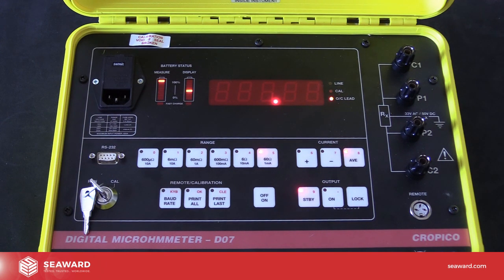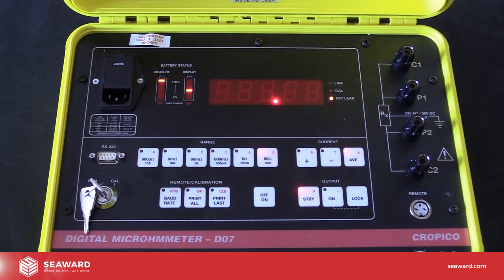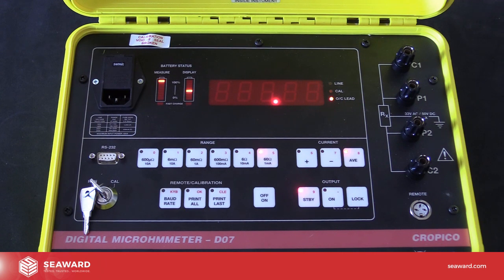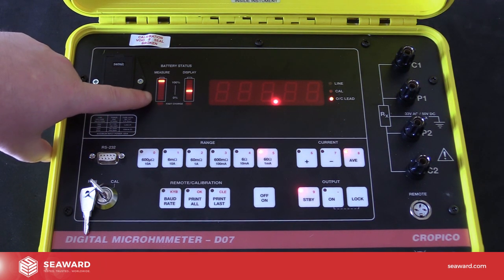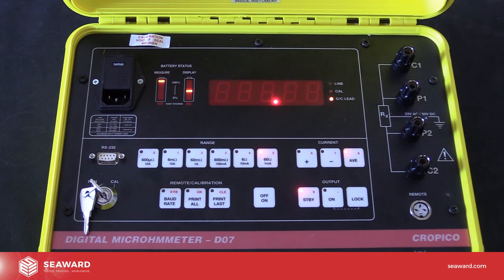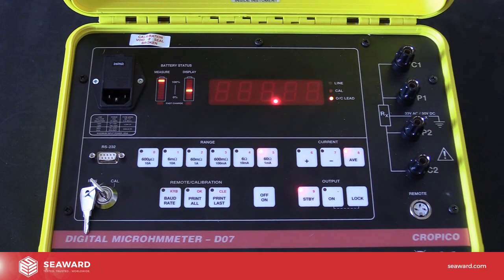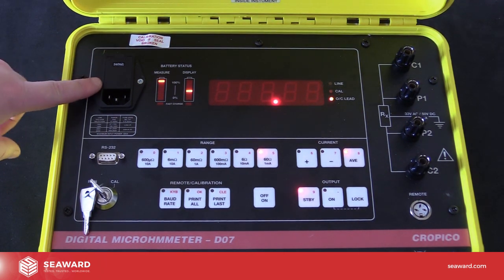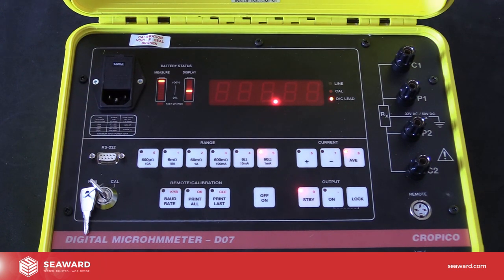The D07 has a large internal battery capable of providing up to 1 hour's measuring on its most demanding 10 amp setting. The device comprises 2 battery gas gauges to tell you how much power you have left within your batteries, one for the measuring circuit and another for the measuring display. The unit can be charged from any mains outlet, including 110 or 240 volt.